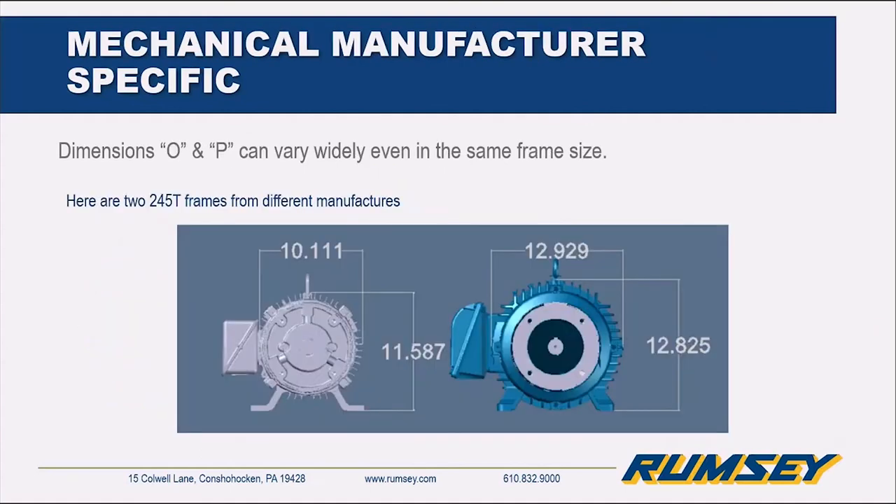Here we have a picture showing how O and P vary within the same frame size. Two different manufacturers, totally different materials — the gray motor is aluminum, whereas the blue one is cast iron. You can see dimensionally they're totally different, but they're both 245T frames. That means they can actually bolt into the same mounting locations without any issue.